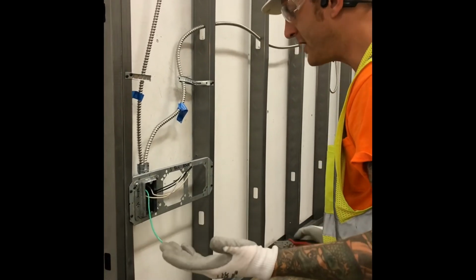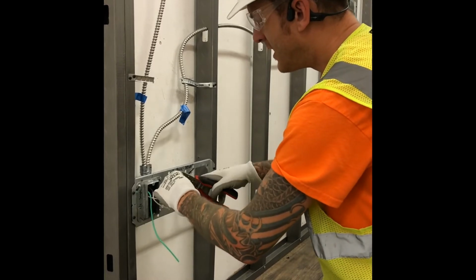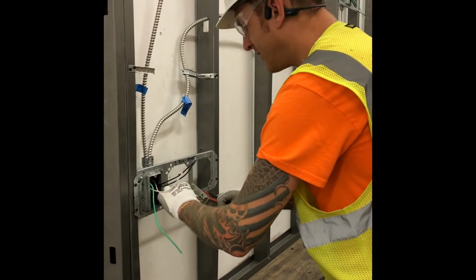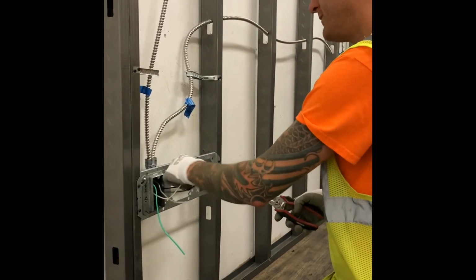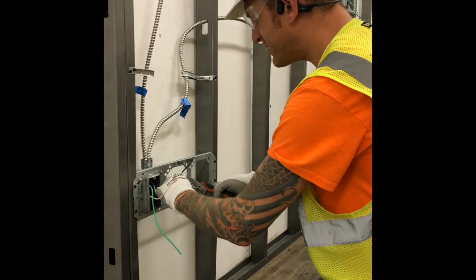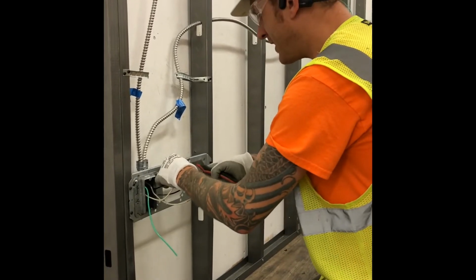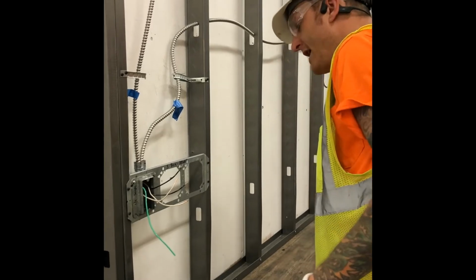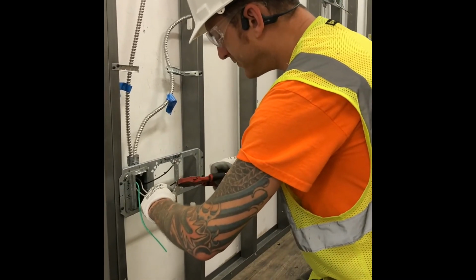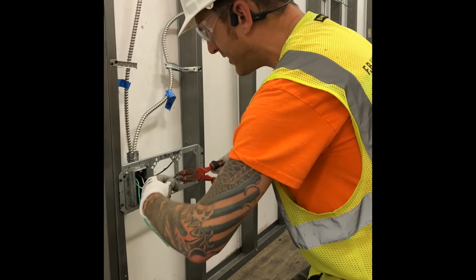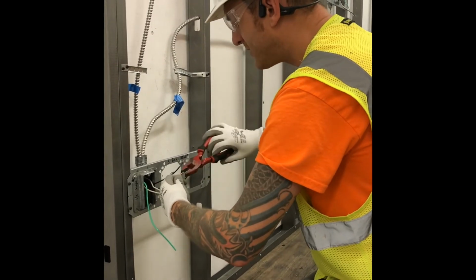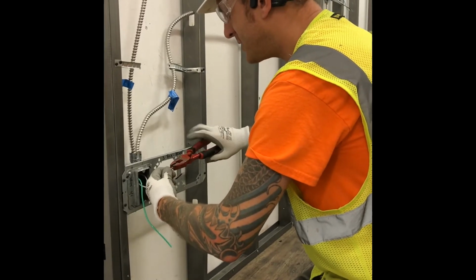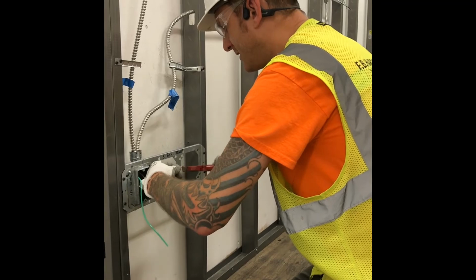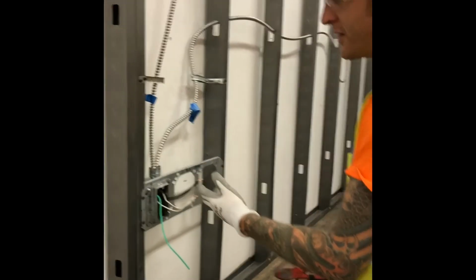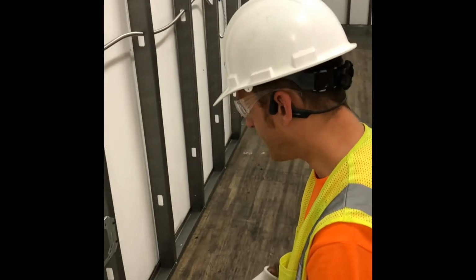If we're not putting the devices on right away, I like to splice the wires together and put them in the back of the box. That way you can test the circuit for continuity later if you need to, or for safety, if someone energizes the circuit, you don't want exposed wires in the box. It's been known to happen where the wrong circuit was turned on, and people went into the box and realized the conductors were energized without wire nuts, which could lead to a shock. So I'll twist that together. Normally these would go directly on a device, you wouldn't want to twist them together like that, but otherwise you'd put two wire nuts on them and push them into the box.